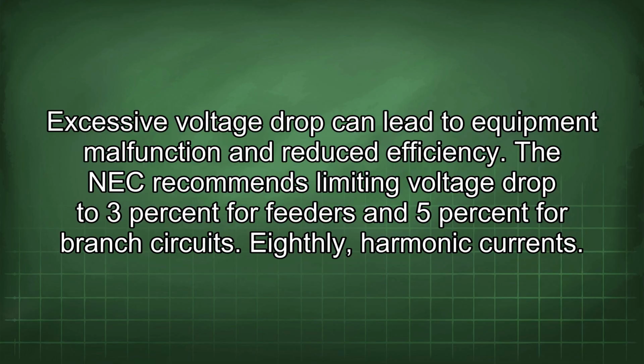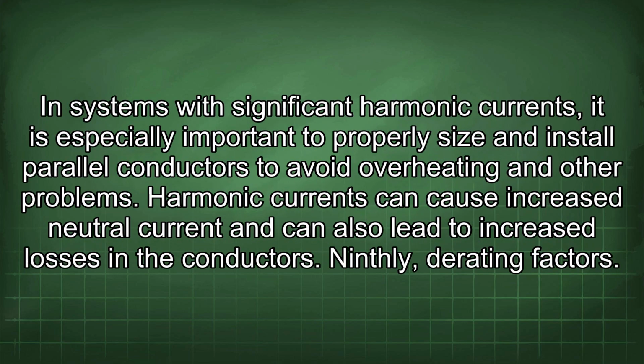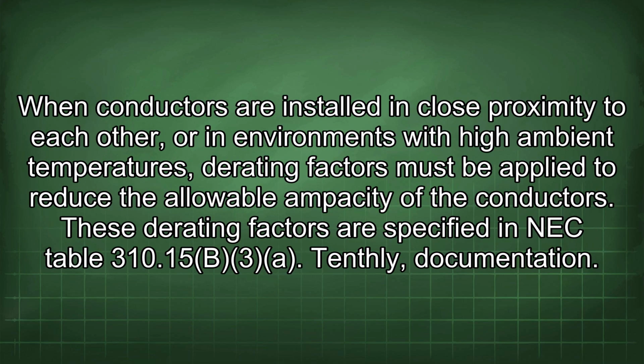Eighthly, harmonic currents. In systems with significant harmonic currents, it is especially important to properly size and install parallel conductors to avoid overheating and other problems. Harmonic currents can cause increased neutral current and can also lead to increased losses in the conductors. Ninthly, derating factors. When conductors are installed in close proximity to each other, or in environments with high ambient temperatures, derating factors must be applied to reduce the allowable ampacity of the conductors.